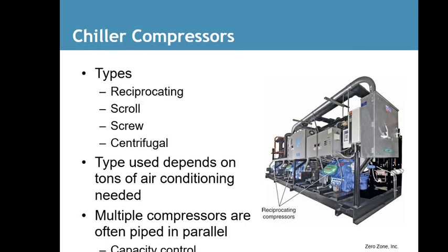Chiller compressor types are reciprocating, like we use in normal air conditioning. They'll just be much larger, and usually they're not hermetic. They're able to be rebuilt. Then there are scroll compressors, screw compressors, and centrifugal compressors. Types are used depending on the tons of air conditioning needed. Multiple compressors are piped in parallel for capacity control.